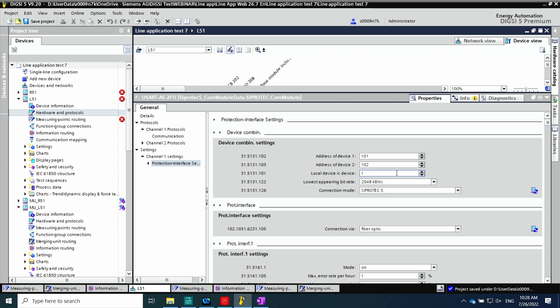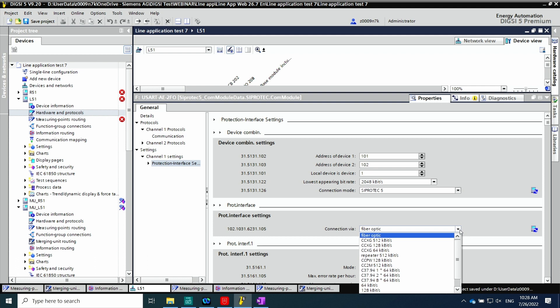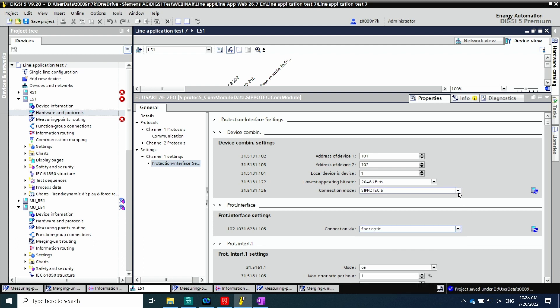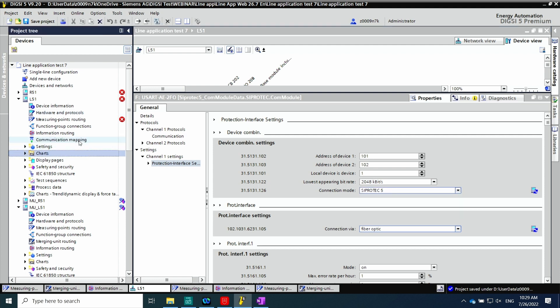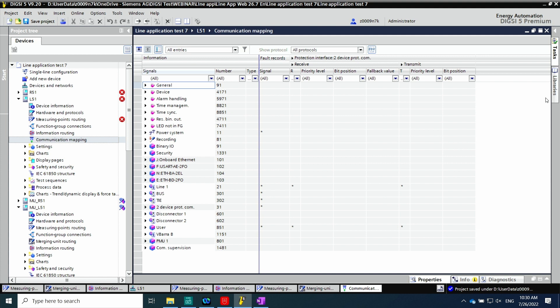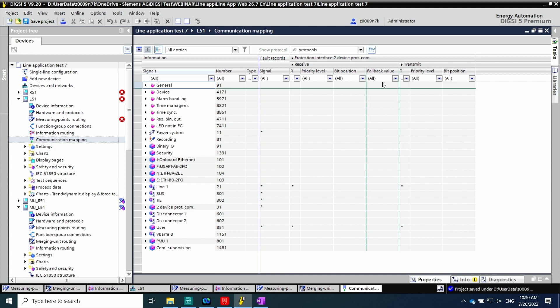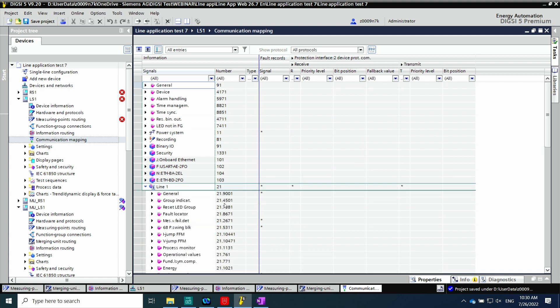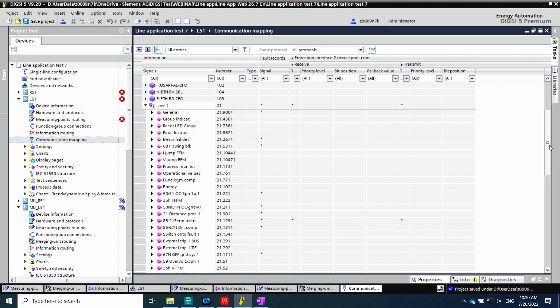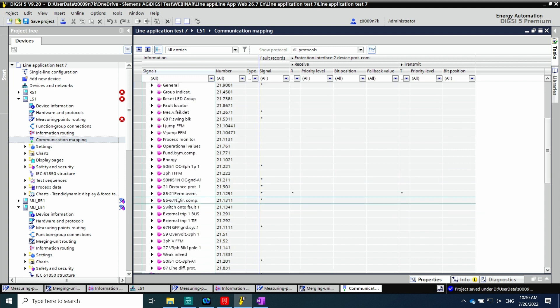We have the communication required for the line differential application — communication between SIPROTEC 5 devices that receive information from process bus networks. Communication with SIPROTEC 4 devices, which receive information from conventional instrument transformers, is also possible. This can be used for brownfield projects where one end has SIPROTEC 4 devices and the other end has SIPROTEC 5 devices via process bus. To transmit information for teleprotection schemes needed for distance protection — for example POTT, permissive overreach transfer trip — the information is assigned in communication mapping.